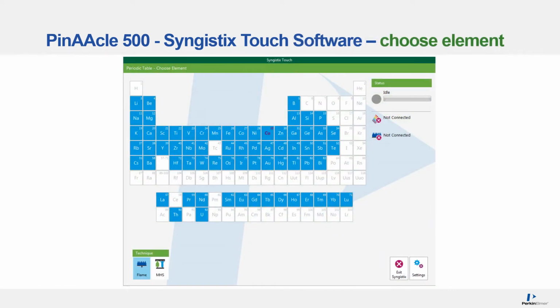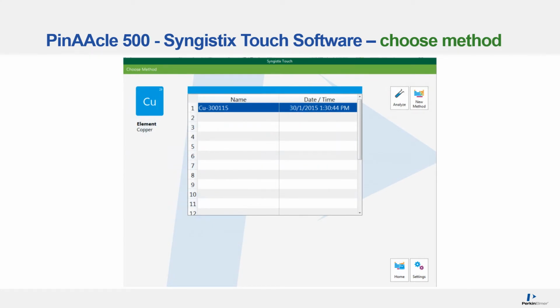When you open the software, you are presented with a periodic table. This periodic table will show you all the possible elements that you could use the Flame AA for analysis. If you have any methods already created, you will see that the element is listed in a purple color. So if the user wanted to, in this case, select copper, there is a method available. Let's pretend that the user has clicked on copper. Now here we can see that the list of methods available for copper includes one method so far. If the user wanted to create a new method, there is a new method button in the top right-hand corner. You could click on that and create your new method and set up all the parameters. But in this case, let's select the currently pre-made method that is available. And we would click on the Analyze button right next to the New Method button in the top right-hand corner.